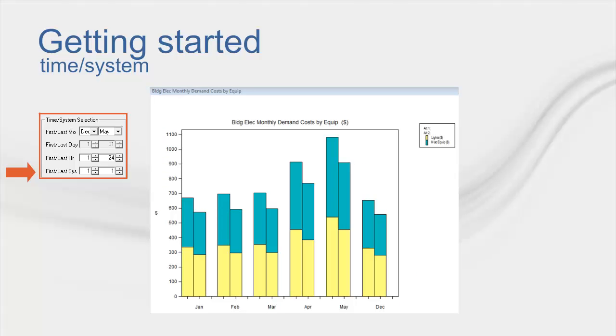The most powerful portion in this section, though, is the first and last system field. The feature is incredible for troubleshooting. This is because, in the ECB and the Equipment Energy Consumption Report, those both only give you the entire building or entire plant's values. In the Visualizer, if you have a plant that is consuming tons of energy, you can break it down even further to figure out the exact system that is causing the issue. Then, you can focus on fixing that system instead of floundering with the entire file or the entire plant.